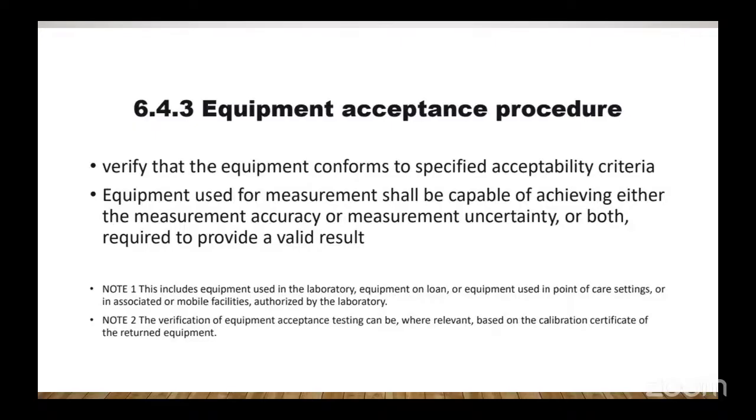Verification of equipment. Even the LIS, you have to verify them, or what is properly known as validation. So there must be objective evidence that checks the characteristic and the performance of that equipment before the equipment is used to run the patient sample. So you cannot just buy an analyzer and run one level of QC or two levels of QC and start using it to run a patient sample. It is not done. That equipment must be validated. It is a crime for you to use any equipment that has not been verified or validated to run a patient sample, no matter the urgency of it.